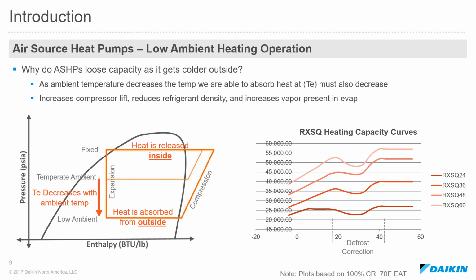So obviously we want to be colder than the air outside so we can absorb heat from it. As that temperature decreases, we're continually dropping that evaporation temperature so we can continue to absorb heat out of it. And there's a few things that happen when we do that. The most significant factor is the density of the refrigerant is decreasing. So it's reducing the volumetric efficiency of our compressor, less mass actually flowing through it. So that's going to contribute to the capacity loss a good deal.